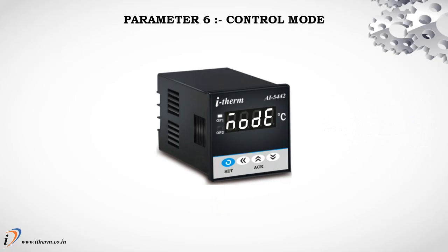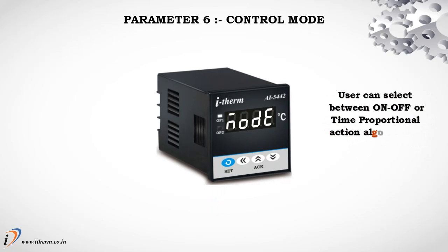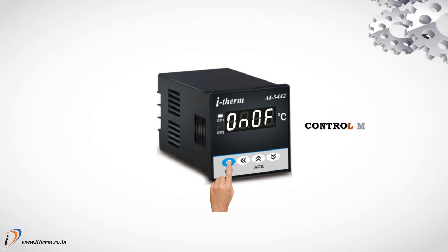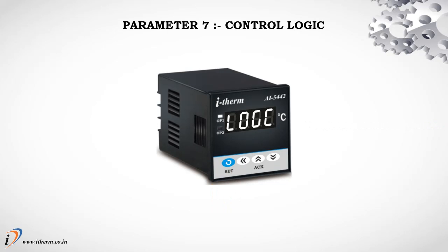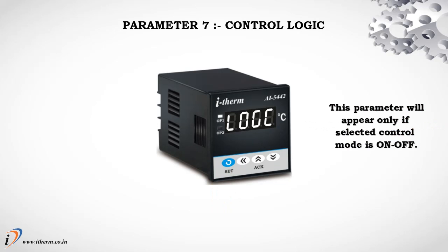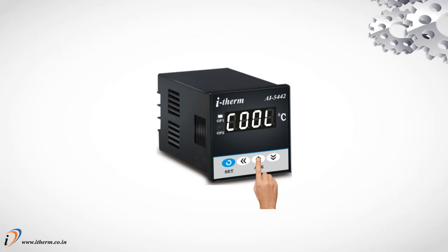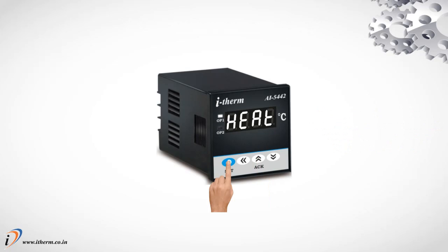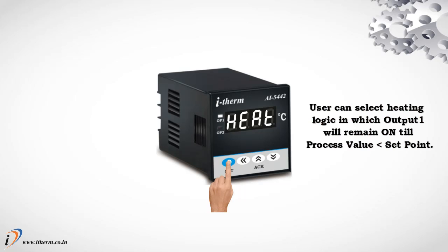Parameter 6. Control mode. User can select between on-off or time proportional action algorithm to be adopted for output. Control mode as time proportional. Control mode as on-off. Parameter 7. Control logic. This parameter will appear only if selected control mode is on-off. User can select cooling logic in which output 1 will remain on till process value is more than set point. User can select heating logic in which output 1 will remain on till process value is less than set point.